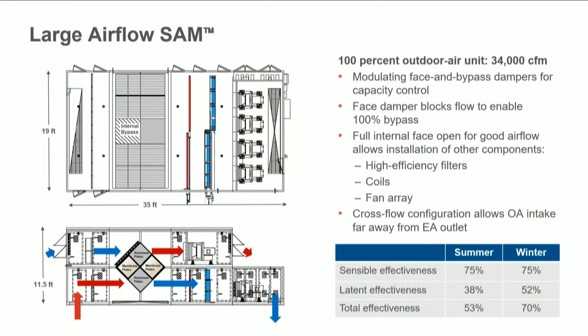For example, here is a 34,000 CFM air handler. The single SAM exchanger includes modulating face and bypass dampers for capacity control. The exchanger has a fully open internal face for good airflow to upstream and downstream components such as high-efficiency filters, coils, or a fan array. For 100% outdoor air units, the cross-flow arrangement allows for the outdoor intake to be far away from the exhaust discharge.